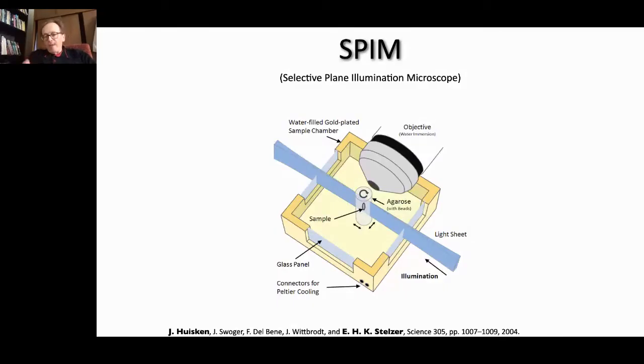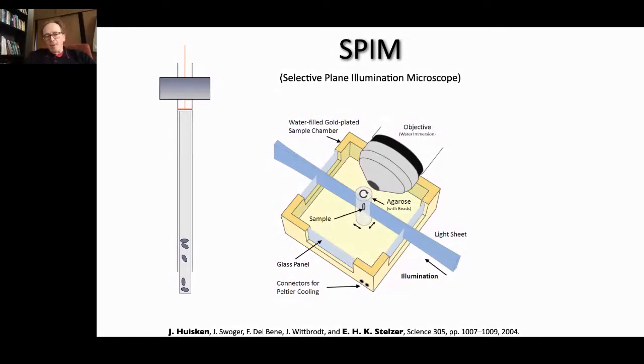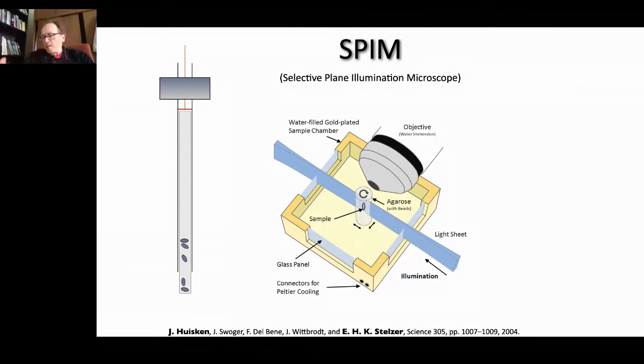SPIM microscopy is distinctive because of how the sample is mounted. In SPIM, it is mounted in a very unusual way — not on a coverslip, but embedded in some kind of semi-solid gel, for example agarose. It is included in a capillary, suspended by gravity in front of the lens, and you create a plunger system to push this agarose column outside of the capillary so that it is immersed in the imaging chamber with no additional glass-water interface. Imaging in SPIM typically happens in an aqueous environment in water, which provides the right environment for many specimens.